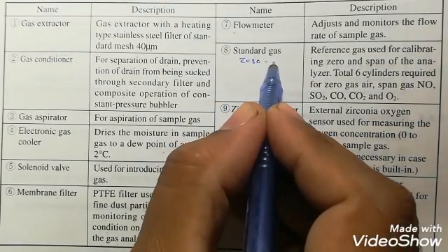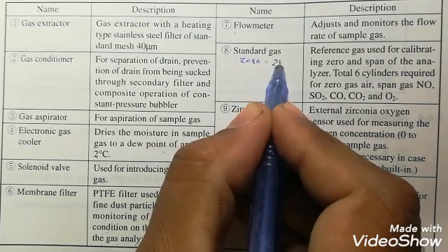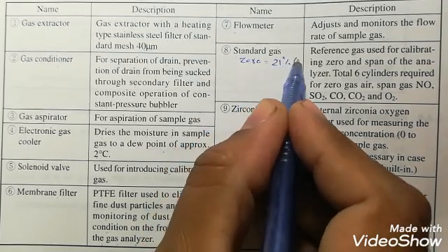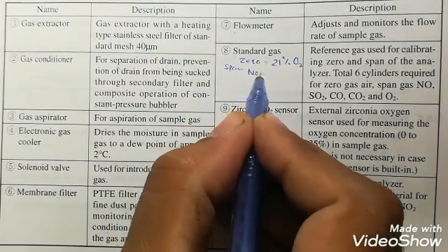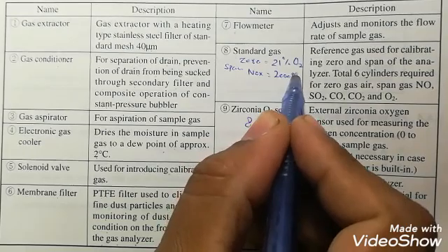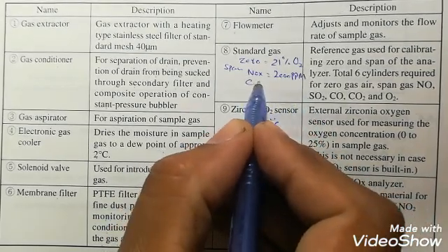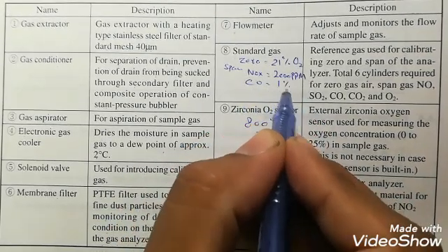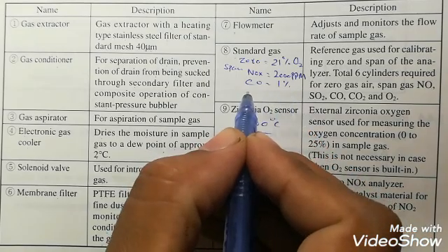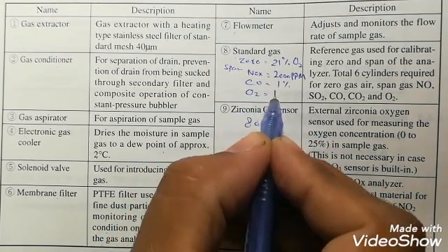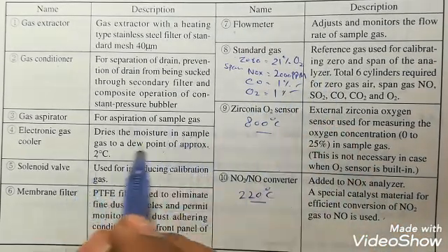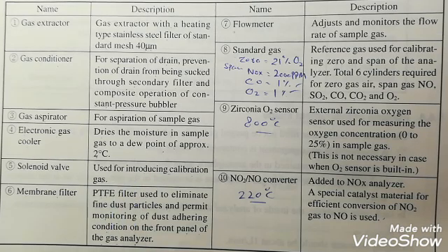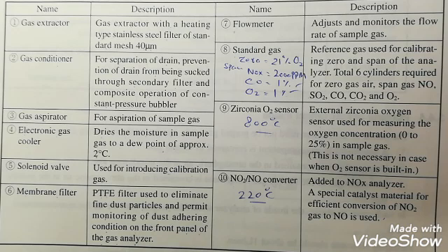Standard gases: for zero, we are using 21% oxygen for zero of all gases. For span, we are using NOx 2000 ppm, CO 1%, and O2 1%. So these are our standard gases we are using for the calibration purpose in this Fuji model. This is the main function of all these parts.